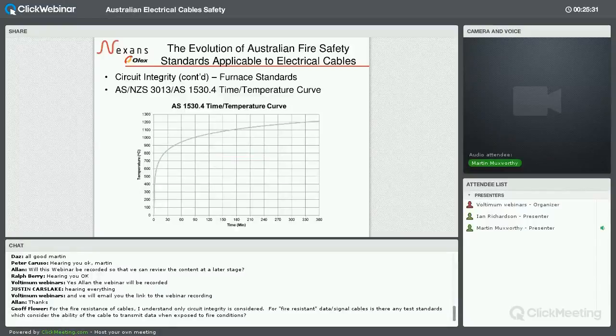It's what's categorized by a cellulose fire. So it's a time and temperature curve that would be typical of a fire started from timber and similar type of building materials containing cellulose. So as you can see, in the 2-hour time period governed by AS 3013, for example, the temperature achieved in the furnace is over 1,000 degrees.